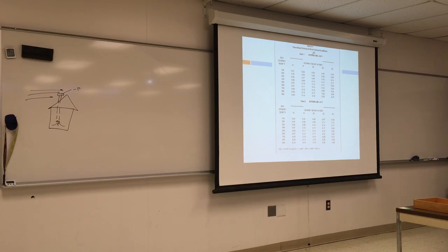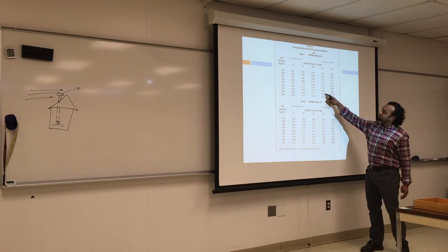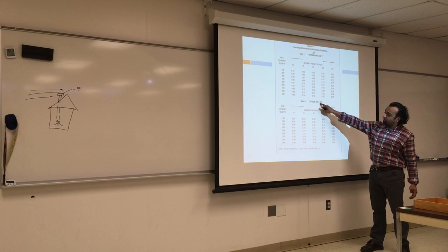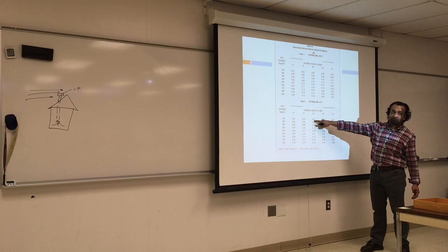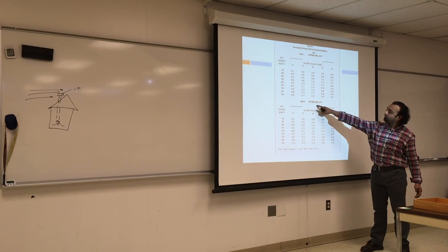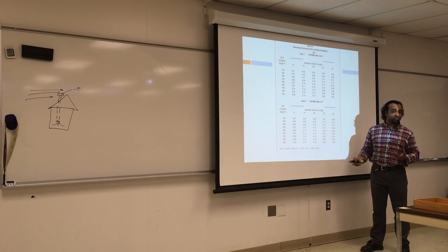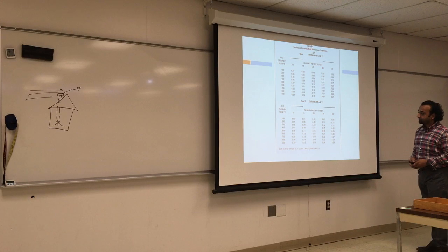Case one. And if you look here, it also depends on the outside temperature. So if the outside is 60, which means it's cold air, this is what you will have as a draft inside your chimney. And this draft actually is in pressure, inches of water. And in case two, if this is 0 outside, this is the draft you'll have. So you'll have more draft if the temperature outside is 0, because the air is completely cold, and the difference in temperature is very big.